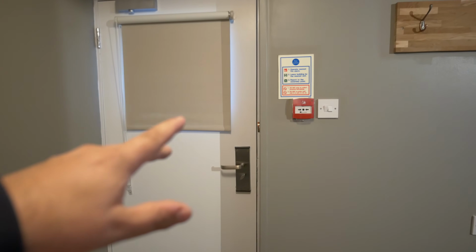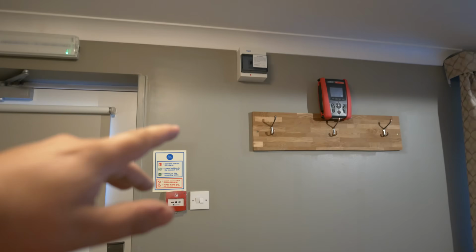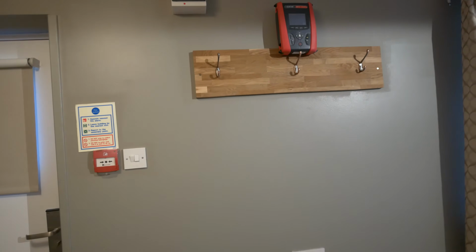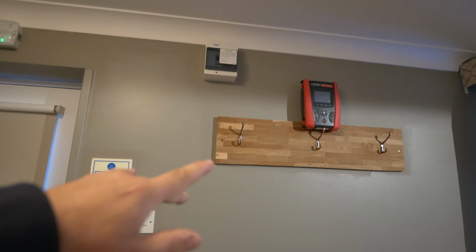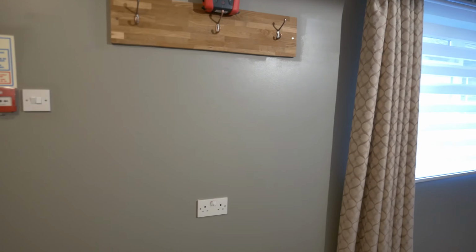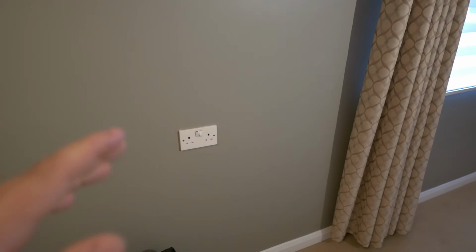First observation would be that we've got a plastic enclosure on the consumer unit. It is pretty close to the point of exit, and this is accommodation that people would pay to come and stay in, so kind of an Airbnb or hotel type arrangement. So there's that consideration if it's a factor, and then basically just wandering around and seeing what accessories we've got.